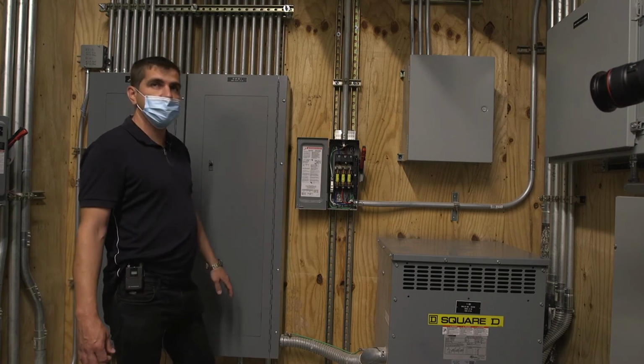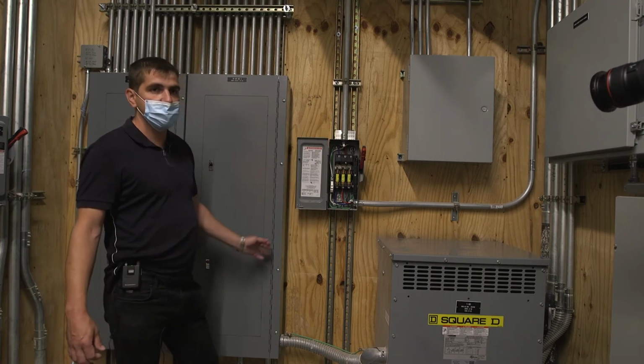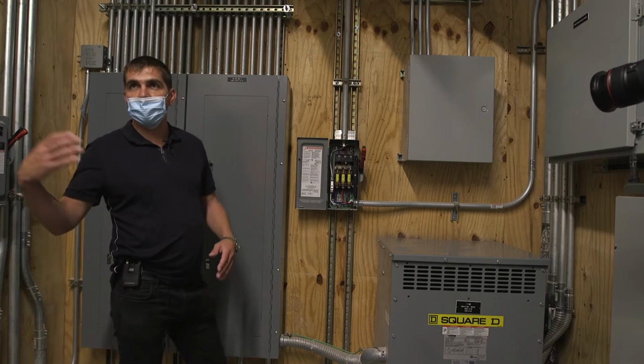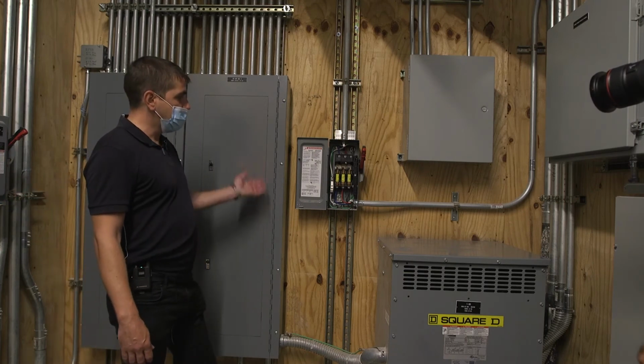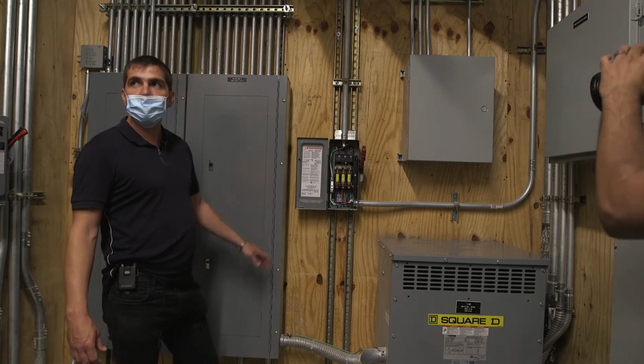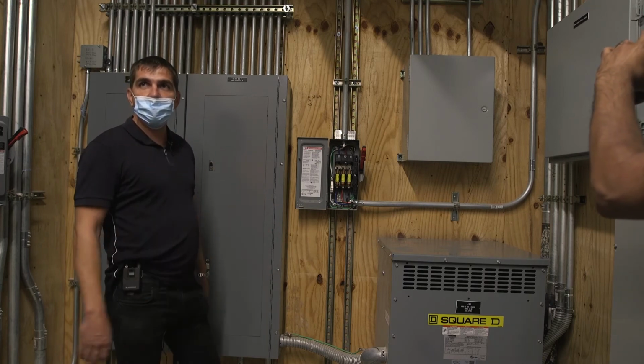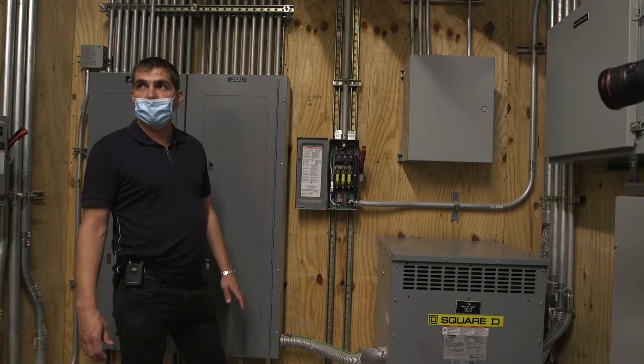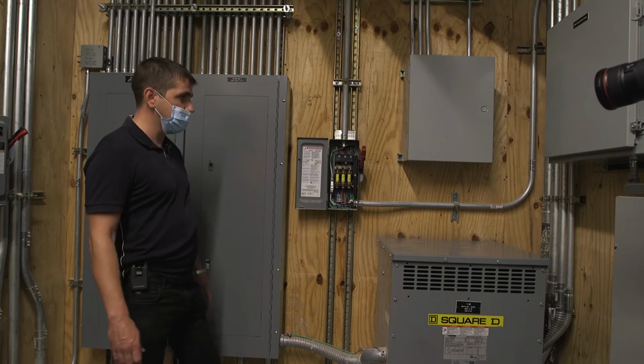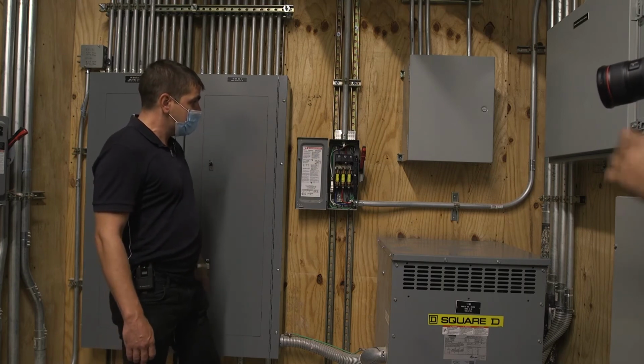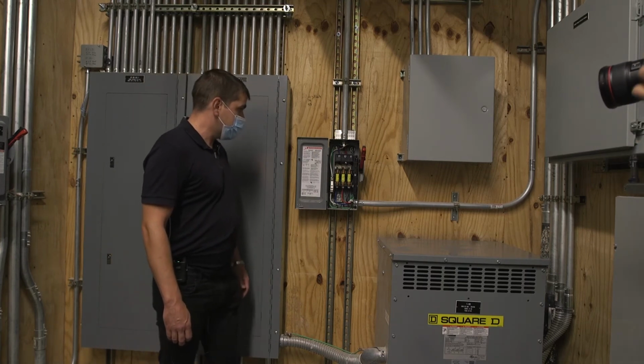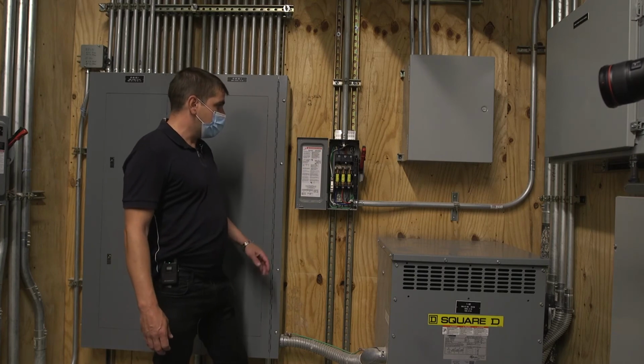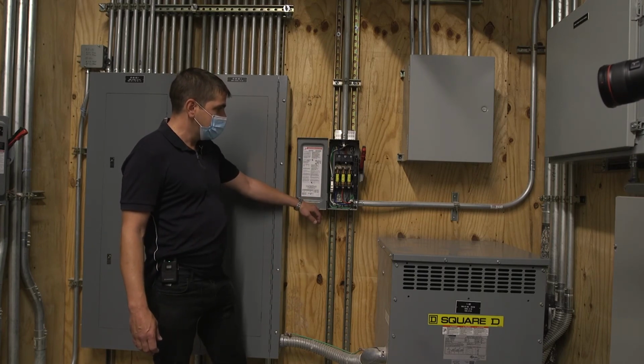So the circuit breaker which serves this fuse disconnect, which is most likely located in the distribution panel upstream, has to be turned off before it's being serviced. The fuse needs to be replaced after the problem is resolved and no short circuit is present. Fuses by themselves don't require any specific maintenance.